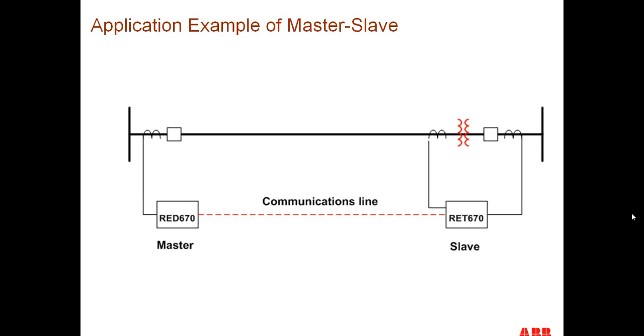If a communication channel is lost, the differential relays become overcurrents. Typically you have your choice. You could set up the line current differential relay so that it comes with a three zone step distance relay, and you can use that for the backup. But you have to provide current and potential transformers for that to work. You can actually have that running in parallel with the line current differential if you wanted to.